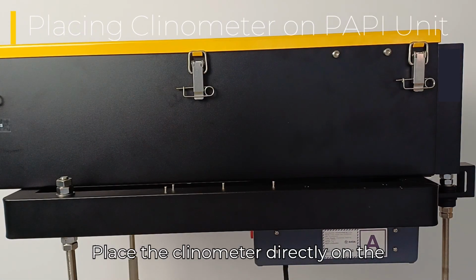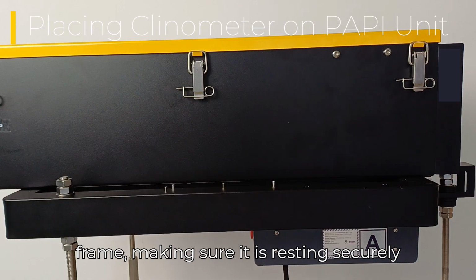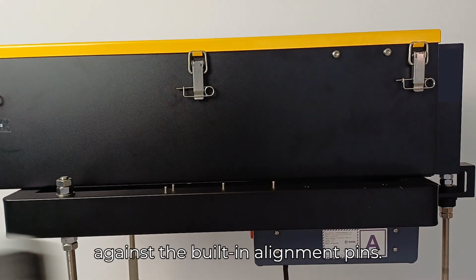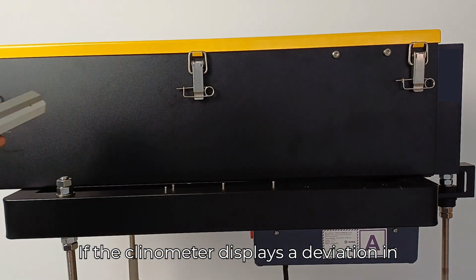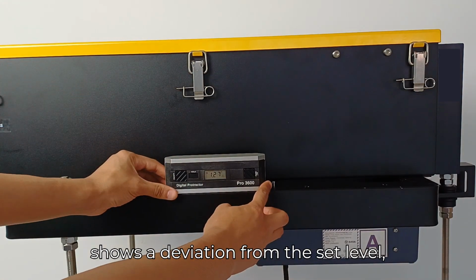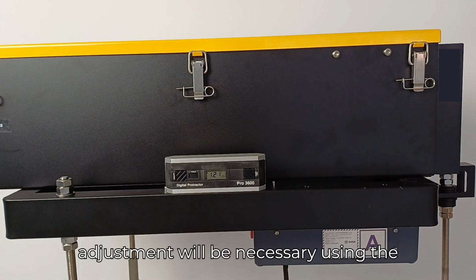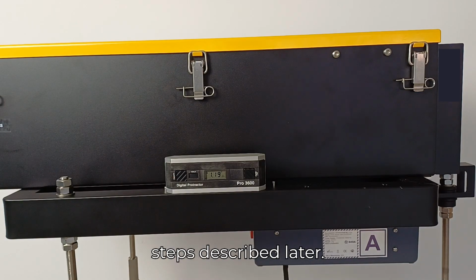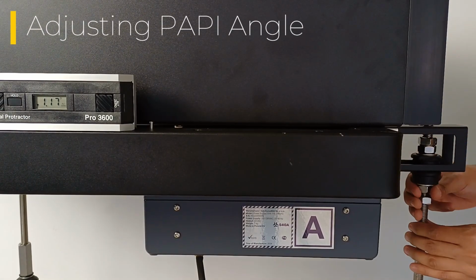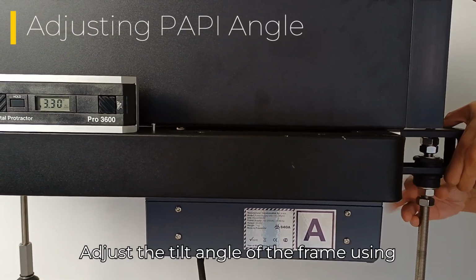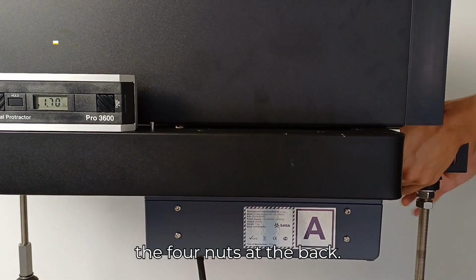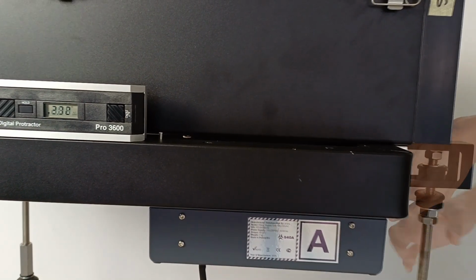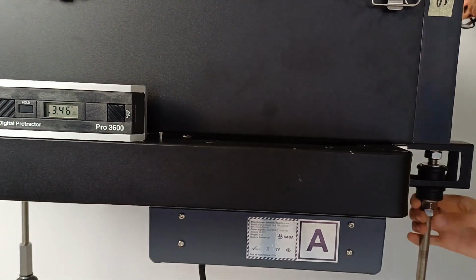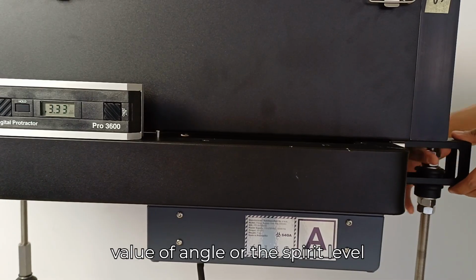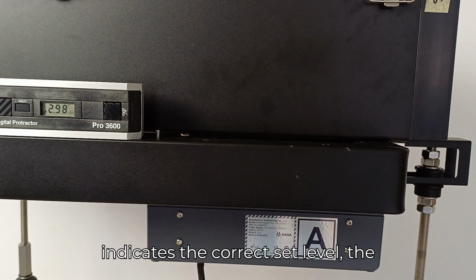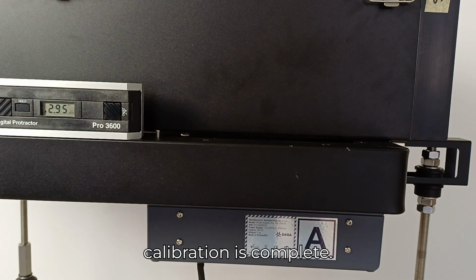Place the clinometer directly on the frame, making sure it is resting securely against the built-in alignment pins. If the clinometer displays a deviation in angle or if the pointer on the leveler shows a deviation from the set level, adjustment will be necessary using the steps described later. Adjust the tilt angle of the frame using the 4 nuts at the back. When the clinometer displays the correct value of angle or the spirit level indicates the correct set level, the calibration is complete.